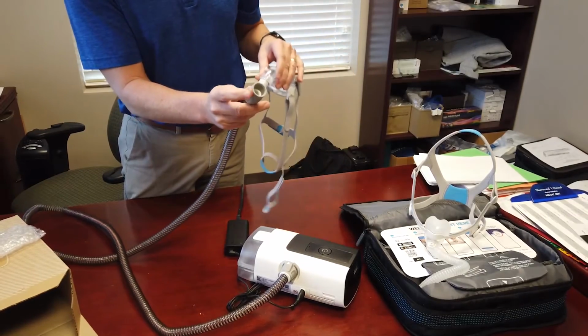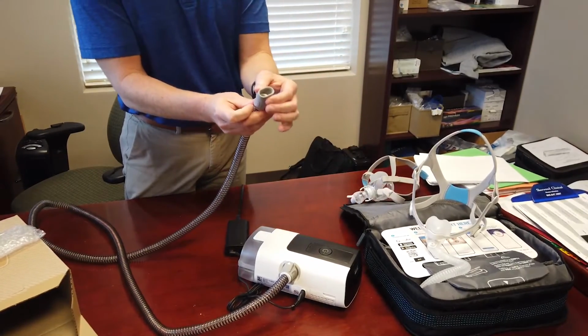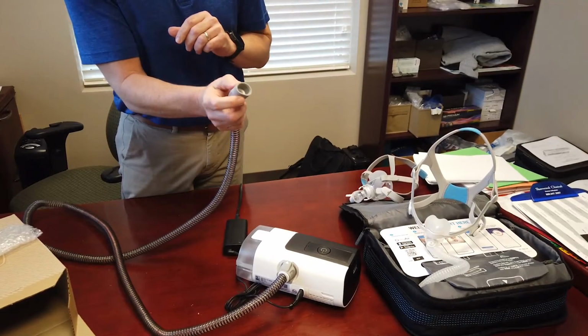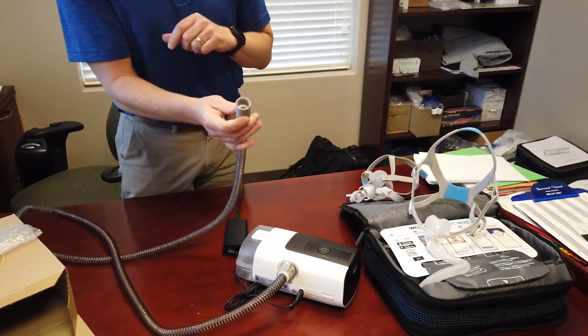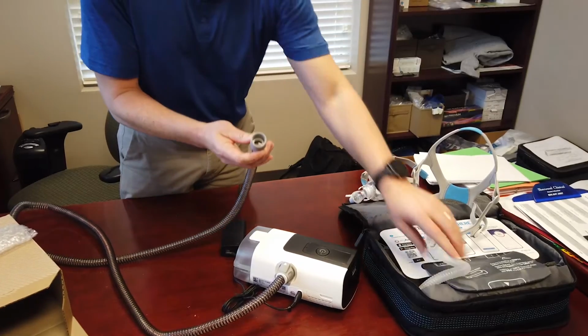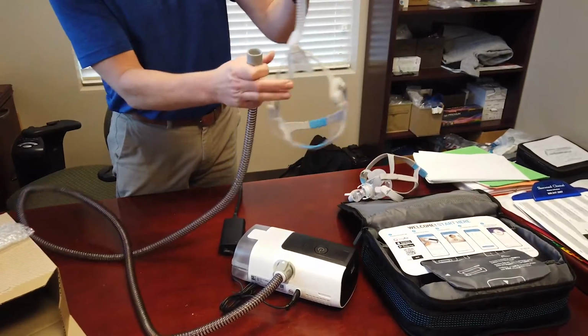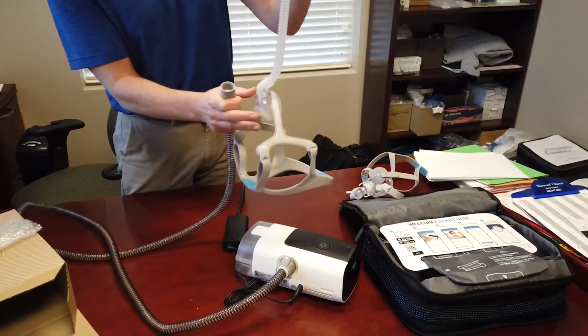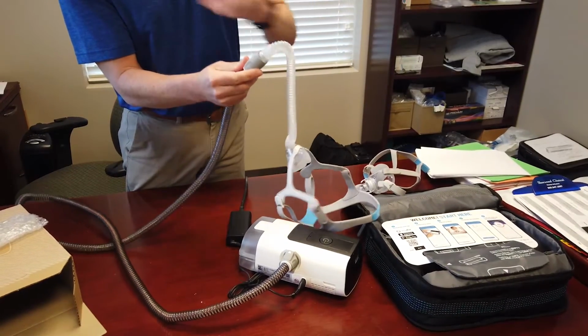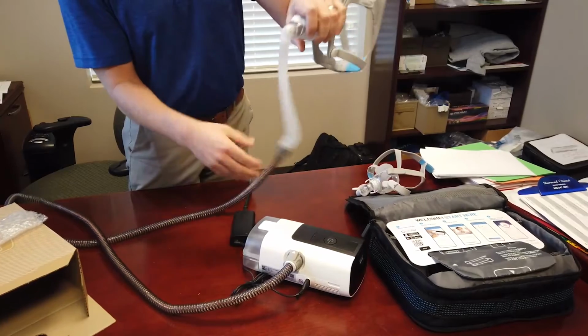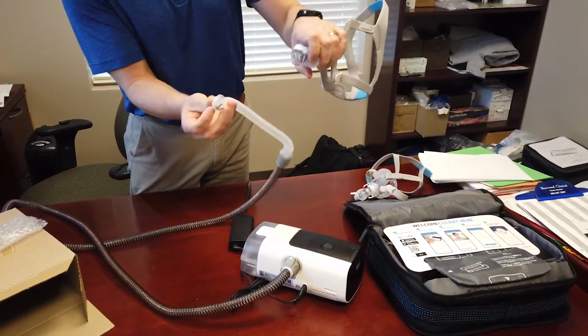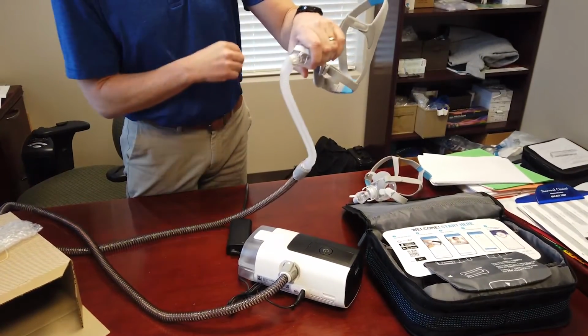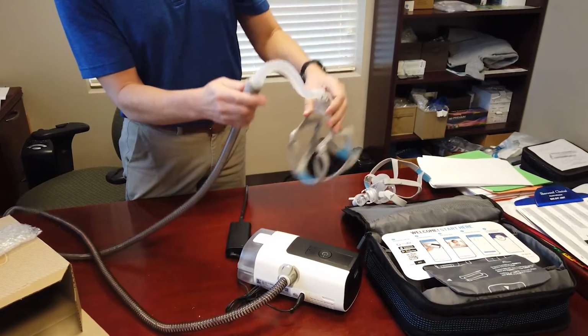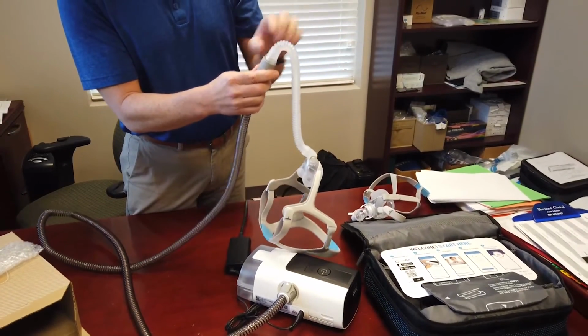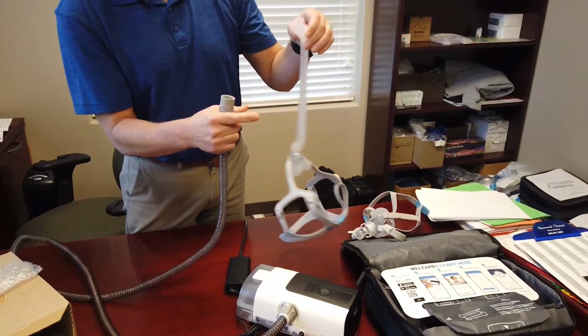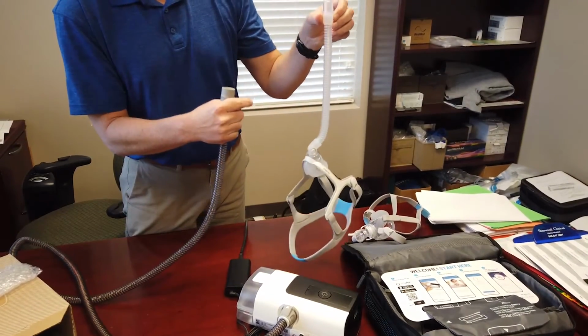And the end of the tubing here, where it's flexible, I don't know if that's rubber or what that is, but it's flexible. The sizing here is standardized, so this will fit any CPAP mask. With our N20, the nasal mask over here, you'll notice the little connection is a bit longer, like an extra foot of tubing, but that slips in all the same. On this particular mask, you have the sides here you can pinch and squeeze and pull that off, and it snaps right back in the front as well. So all masks will fit this tubing because the connection is standardized, but again, you have to make sure that the elbow is specific to the mask you're using.